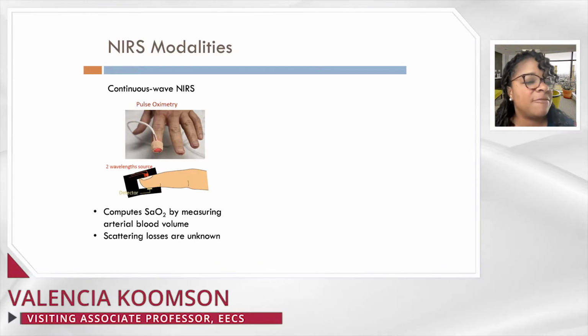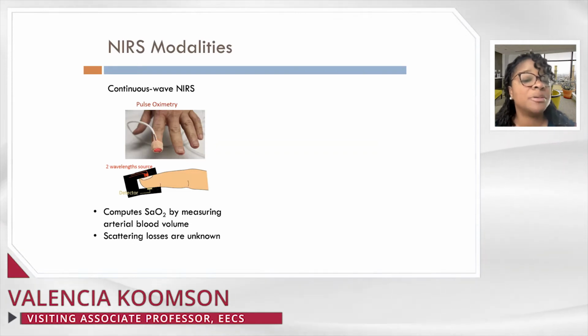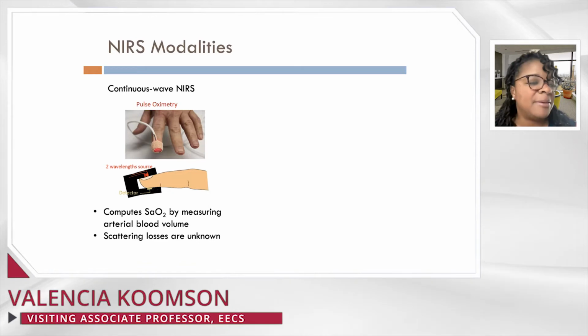In continuous wave NIRS measurements, low frequency or DC near-infrared optical signals are applied to the tissue, and we measure the amount of absorption of biological chromophores. But scattering losses cannot be measured directly in this method. Relative changes of hemoglobin concentration can be extracted by applying a differential form of what we call the modified Beer-Lambert's law. The most significant advantages of continuous wave NIRS are the simple hardware and low cost and compact design.